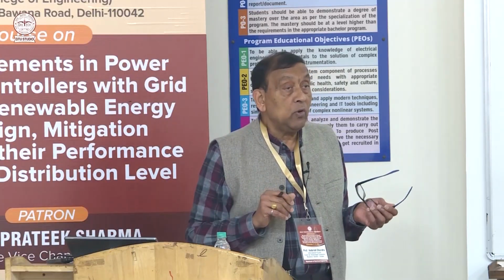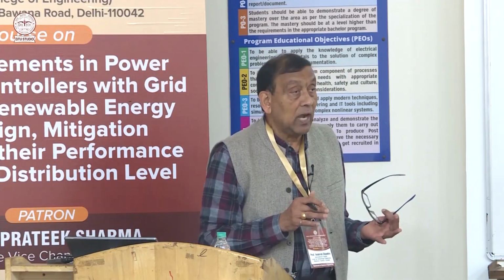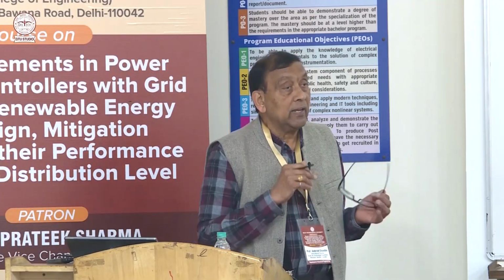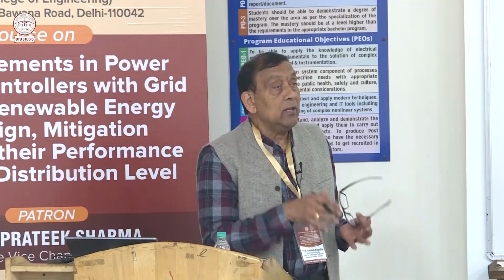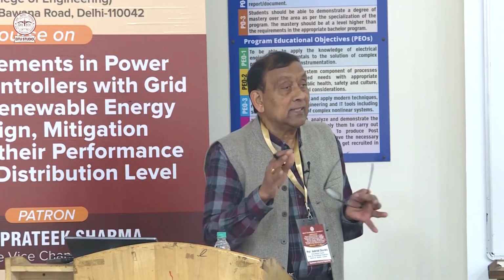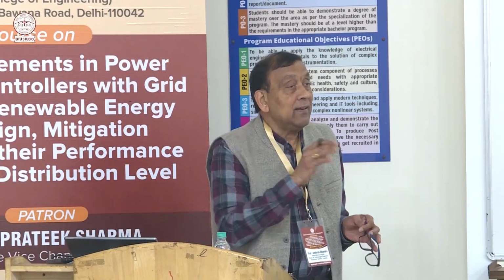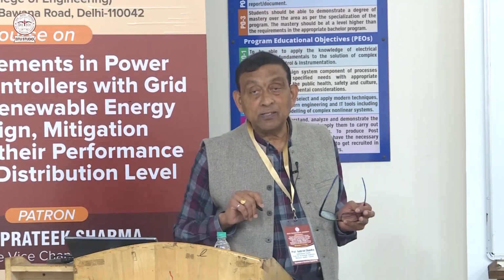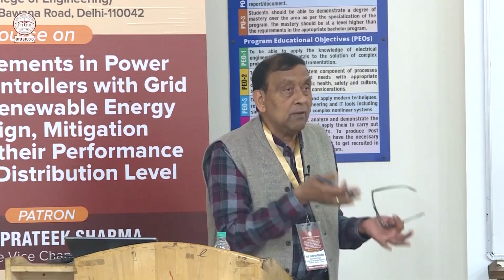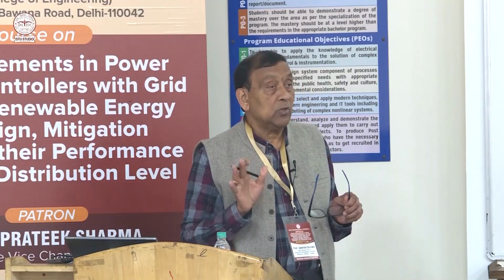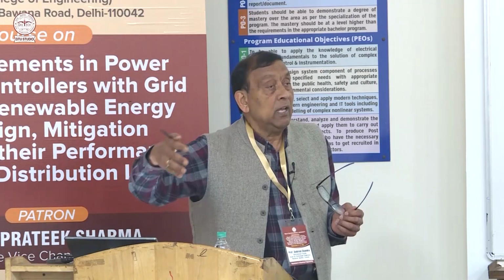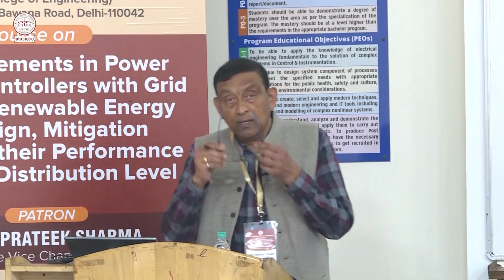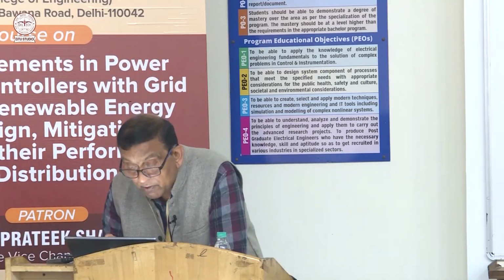Initially you don't want to invest in a 3-phase transformer for 90 MVA. It will be a very costly investment in the beginning. So you can start with only 2 single-phase transformers, and instead of having a delta connection, you can have a VV connection, which will give you 58% capacity. And then after a few years you can buy the 3rd transformer. So this is how you can delay the capital you are investing.